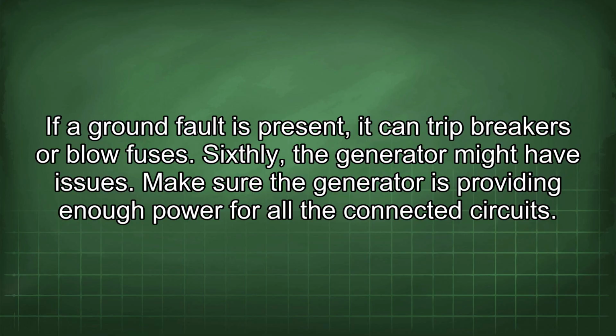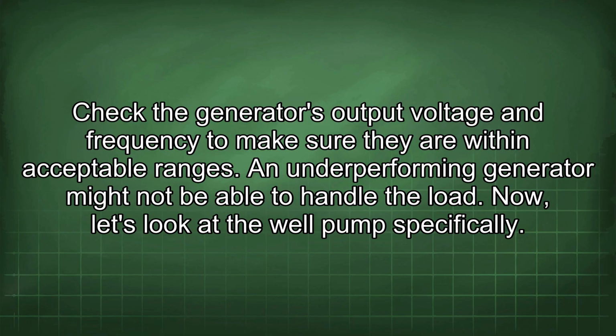Sixthly, the generator might have issues. Make sure the generator is providing enough power for all the connected circuits. Check the generator's output voltage and frequency to make sure they are within acceptable ranges. An underperforming generator might not be able to handle the load.